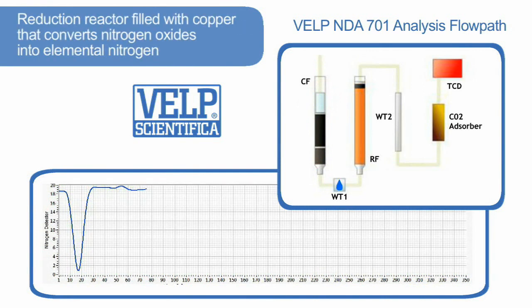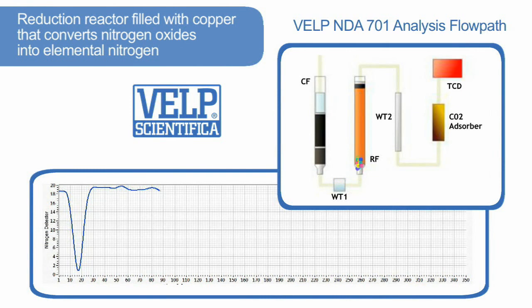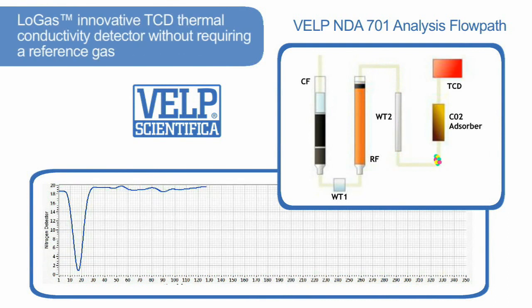The gases pass through the reduction reactor, filled with copper, which converts nitrogen oxides into elemental nitrogen at 650 degrees centigrade. Any remaining water is completely absorbed by the second chemical water trap. A maintenance-free auto-regenerating CO2 absorbing system ensures the elimination of all CO2. Finally, the remaining elemental nitrogen is detected by the innovative LoGas TCD thermal conductivity detector, without requiring a reference gas.